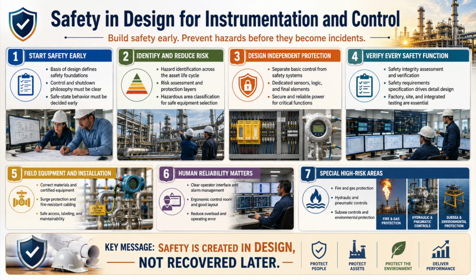Control rooms must support visibility, communication, access, maintenance, and future growth. Safety actions should be physically and visually distinct from routine controls. Equipment rooms need realistic space for panels, cable entry, heat dissipation, expansion, and safe working access. Space that appears generous during early design usually shrinks after supplier data, electrical equipment, structures, stairways, and cable routes are added. Packaged control panels require particular scrutiny.